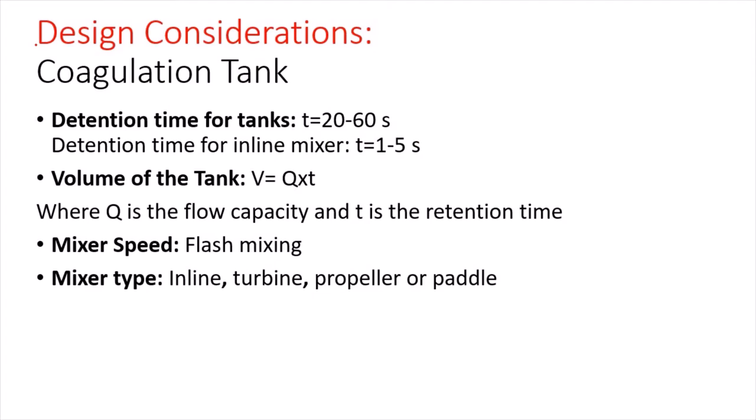Let's begin by the design considerations of the coagulation tank. Concerning the detention time for coagulation tanks, it's between 20 and 60 seconds. So what does detention time mean? It means that the water has to stay within the coagulation tank for about 20 to 60 seconds.